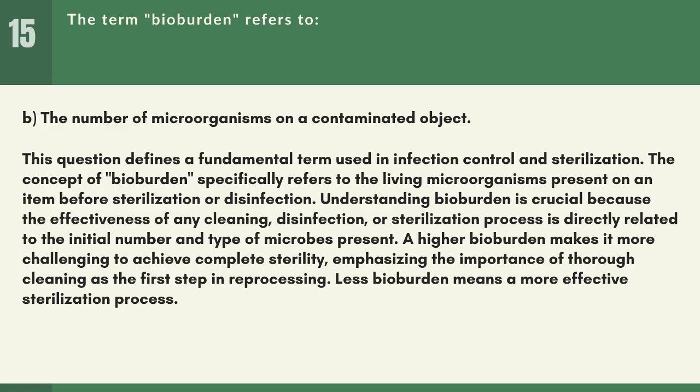Understanding bioburden is crucial because the effectiveness of any cleaning, disinfection, or sterilization process is directly related to the initial number and type of microbes present. A higher bioburden makes it more challenging to achieve complete sterility, emphasizing the importance of thorough cleaning as the first step in reprocessing. Less bioburden means a more effective sterilization process.